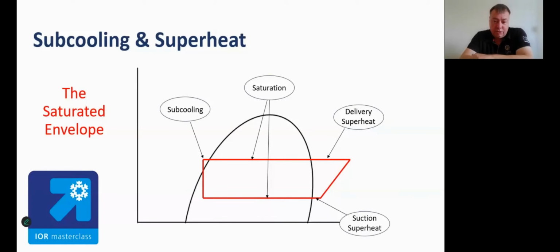And most of you will be familiar with this, and this shows where on the pressure enthalpy diagram these different states of refrigerant are. So we have saturation in the middle, two different pressures, two different temperatures, and that's in the condenser and the evaporator, which if we've got a good system, that's the only places that saturated liquid and vapor should be.